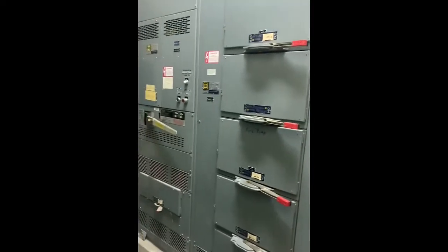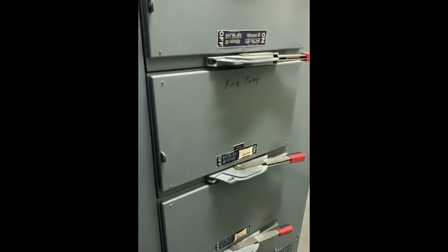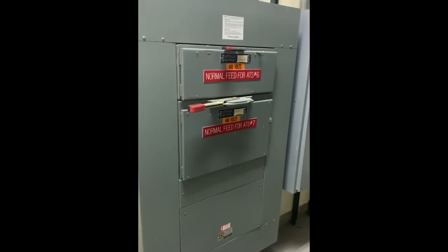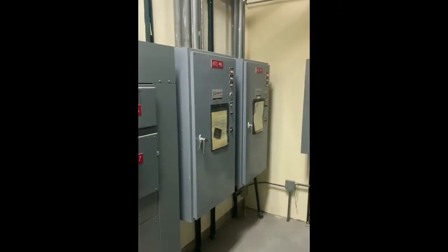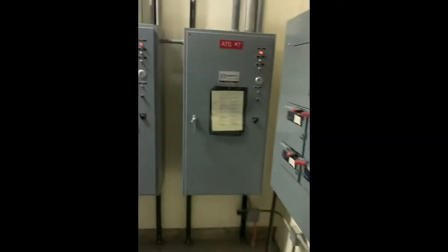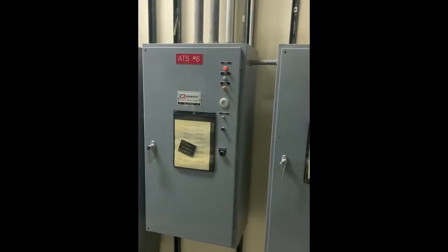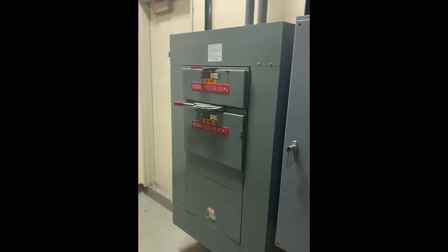This is the switchgear for the emergency generator. It's got overcurrent protection, and then it's got the fused buckets that connect to the feeds for the different transfer switches, fire pump, and all the other loads associated with it. Turn around here. Here's the normal feed for a couple of ATSs, automatic transfer switches, which are located in this room. Let me go around this way, make it a little easier to see. All right, ATS 7, ATS 6. Normal feed from ComEd.